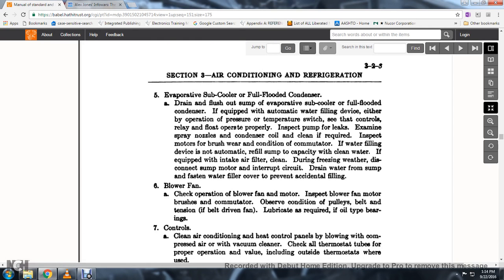5. Evaporative subcooler or fully-flooded condenser: drain and flush the sump of evaporative subcooler or fully-flooded condenser. If equipped with automatic water filling device with pressure/temperature switch, check that the controls, relay, and float are operating properly.